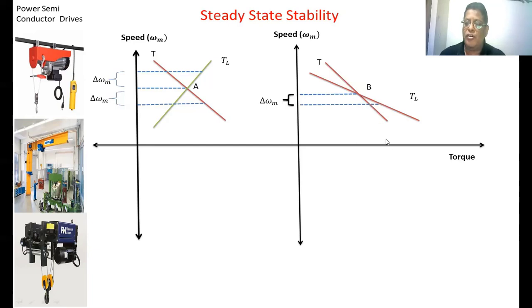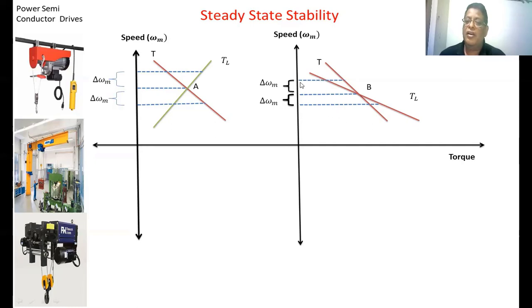From the corresponding point, the load torque is more than the motor developed torque. So again the motor will be decelerated — the speed of the motor will further decrease and it is not coming back to the original speed. Now if we increase the speed, the motor torque as well as the load torque change: the load torque will be less than the motor torque, so the speed of the motor will further increase. The operating point will go up and it is not coming back to operating point B.